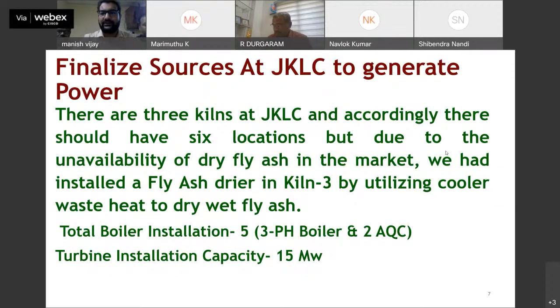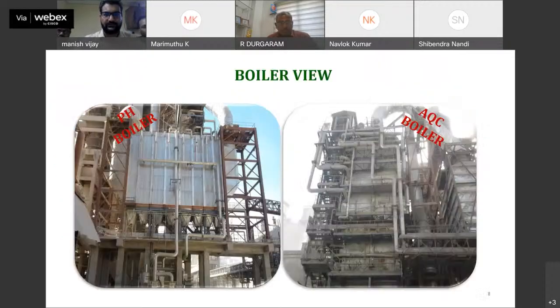As we have three kilns, in the initial decision we had decided to install boilers on all three kilns. But as we had already installed a fly ash dryer system to dry fly ash in our line 3, we chose three preheater boilers on our kiln sides, and line 1 and line 2 for AQC boilers. The total generation capacity is around 15 megawatts from these 5 boilers. These are the views: horizontal boilers for the preheater side and vertical boilers for the AQC side.